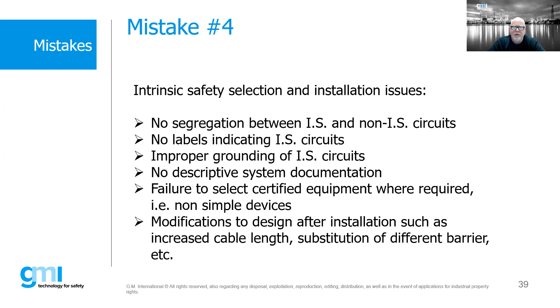So looking at these two pictures here, what we see on the left-hand side is we have IS and non-IS within the same enclosure, which is fine. We can do that. We maintain a separation of 50 mil segregation between IS and non-IS. And what we've done with regards to the positioning of the glands, right? This is a 50 mil separation. This is power over here. This is IS over here. But then we've kind of screwed this whole thing up by running our IS and non-IS against each other. So we cannot do that.